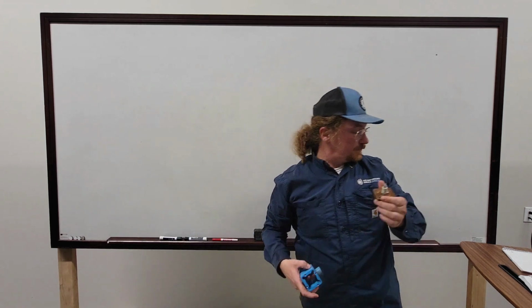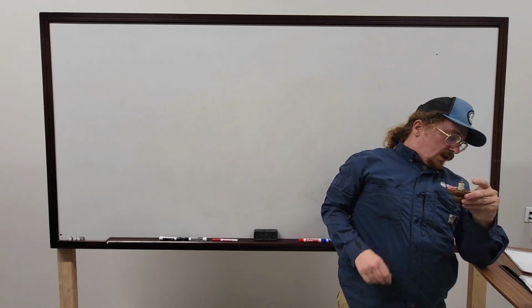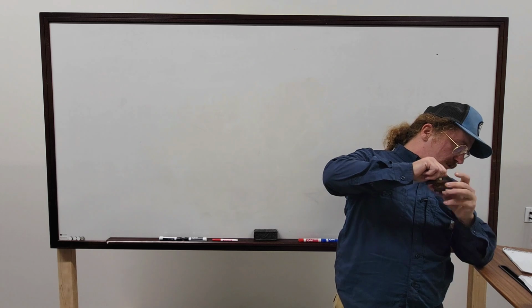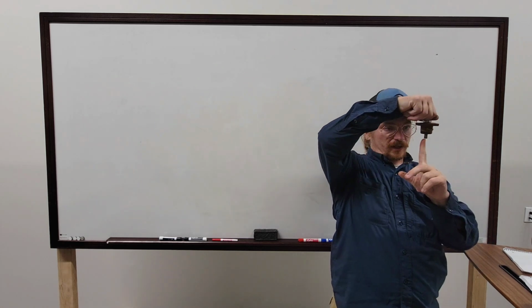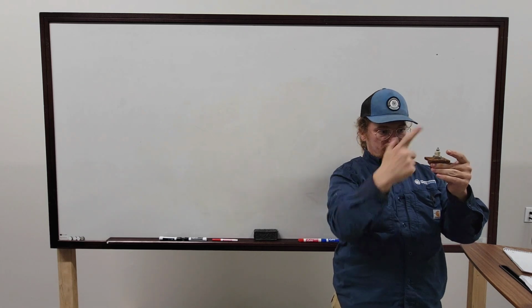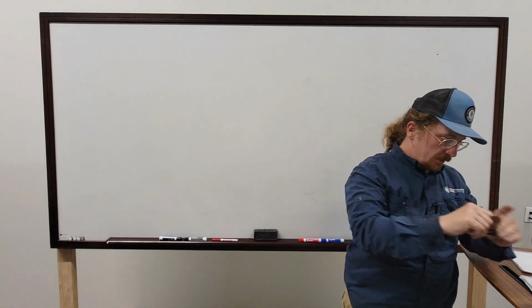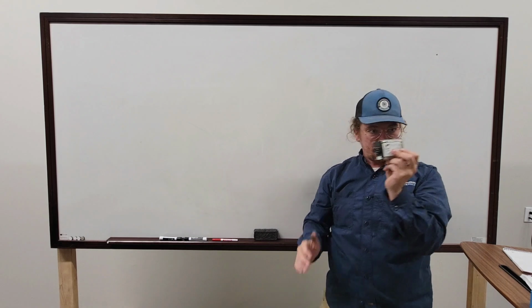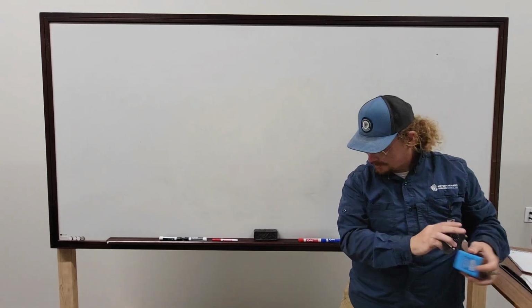All right, so this is what it would look like, the low water electrode style, where there's actually an electrode right here. You have contact here, so that when we make continuity, when we break continuity, we open a set of contacts. And it's typically something like this, plugged in the wall, a strange relay. It's got a bunch of weirdness to it.